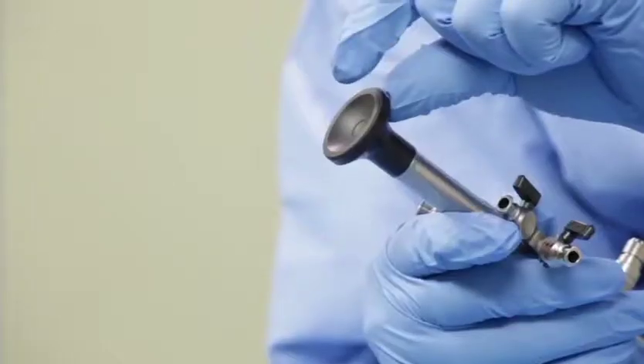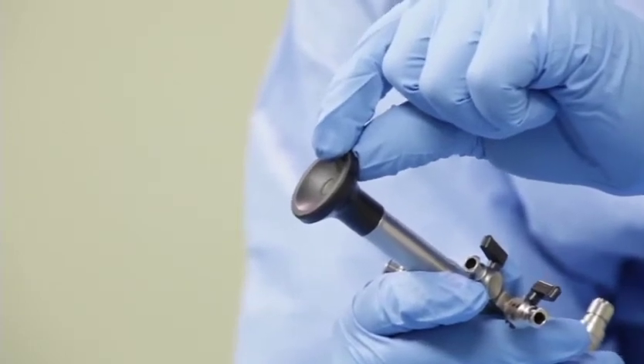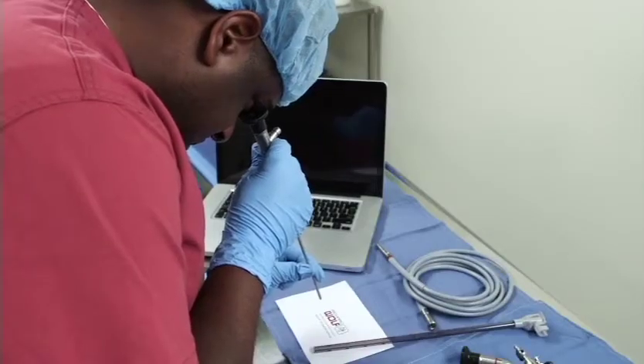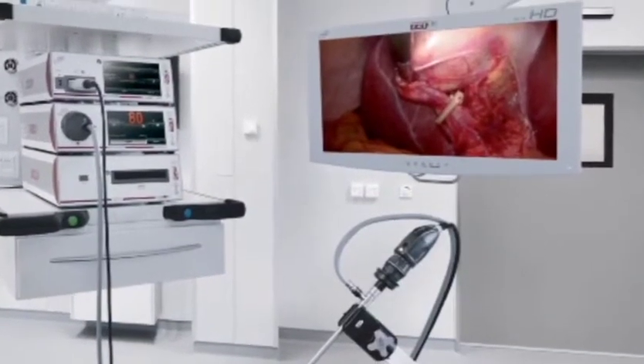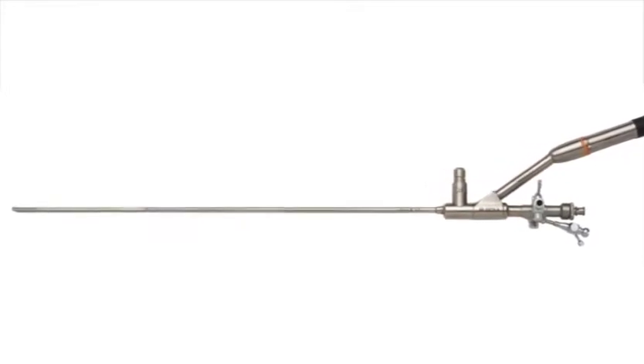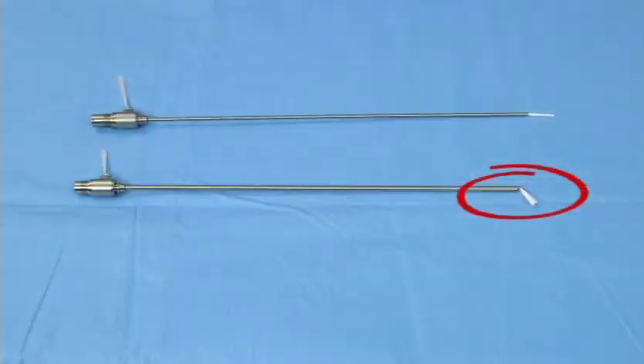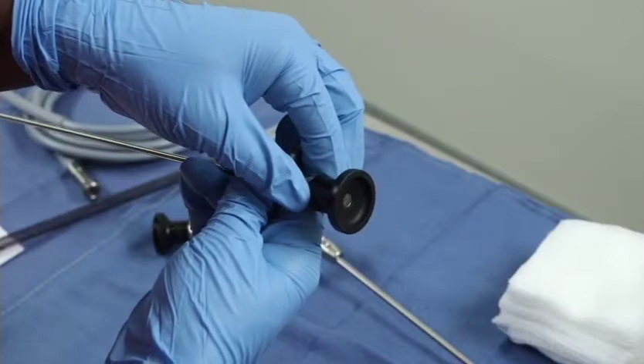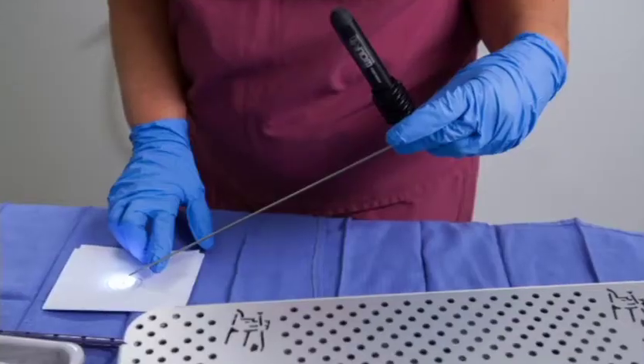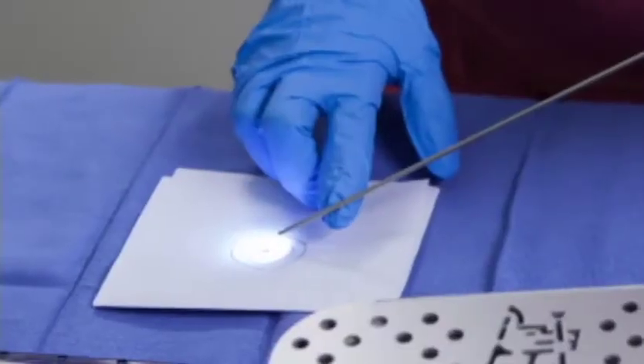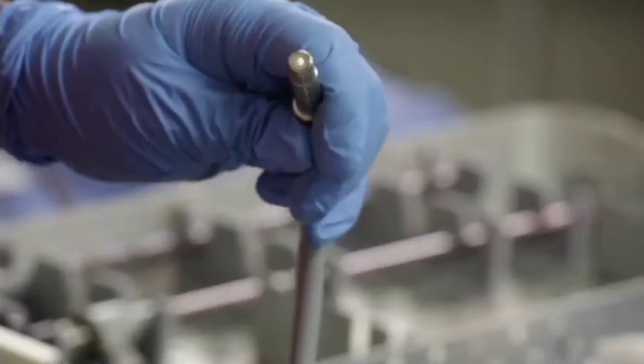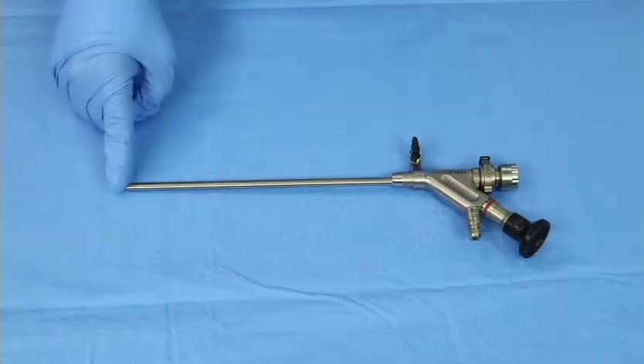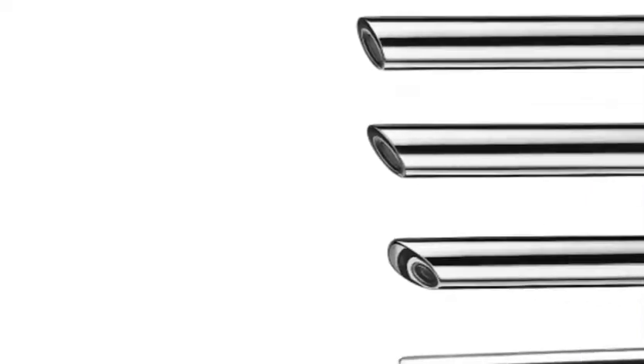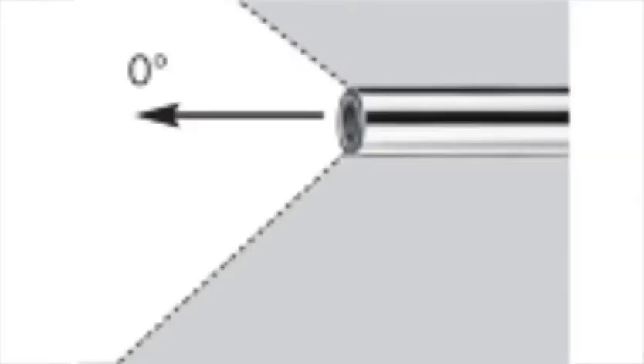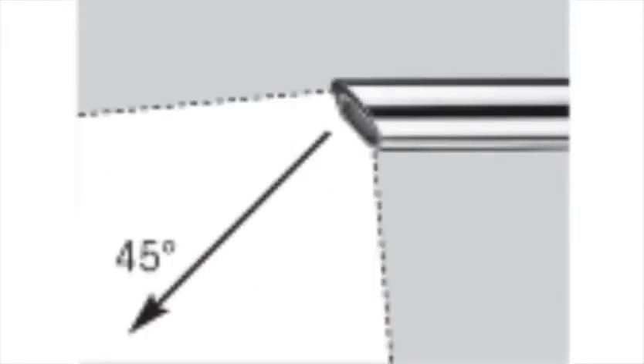an objective lens. Each rigid endoscope has an eyepiece that allows the surgeon to view the operative site, either by looking directly into the eyepiece or by attaching a camera that projects the image onto a monitor. The shaft of the endoscope is located between the eyepiece and the objective lens. The shaft is metal and houses the light fiber bundle and the optical bundle or optical chain. Connected directly next to the eyepiece is the light post. Fiber optic light fibers are bundled together to transmit light from the light post to the distal end of the scope via a light cable attached to the scope's light post. The objective lens, located at the distal end of the endoscope, determines the angle of view for the surgeon, such as forward or 0 degree, lateral, oblique, or retrograde.